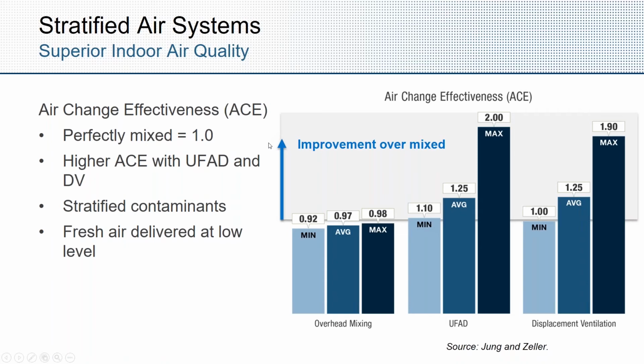So on that note, there's a study done a couple years ago that looked at air change effectiveness, which is essentially how quickly does the air get from the supply point to the breathing zone in comparison to the supply point to the return. In a mixed system, you would expect that to be nearly equal, and it's just the ratio of those two time constants. Unity, or 1.0, would be expected of a mixed system, but with UFAD and displacement, you can see that the average is about 30% better throughout the floor.